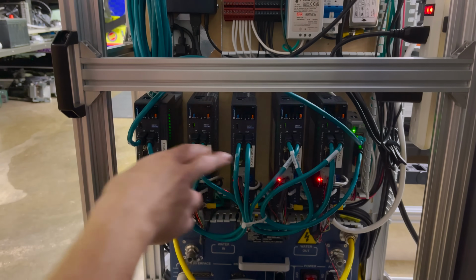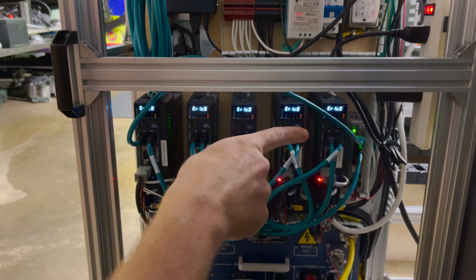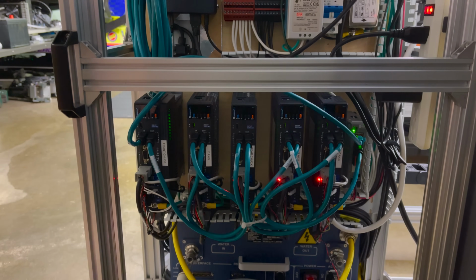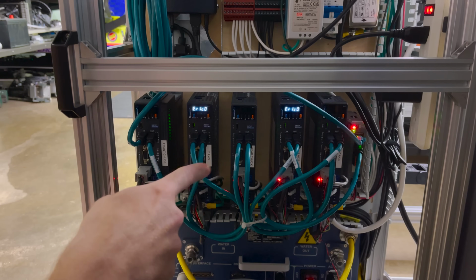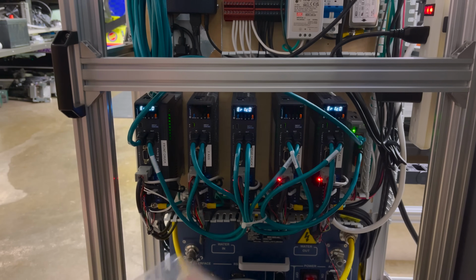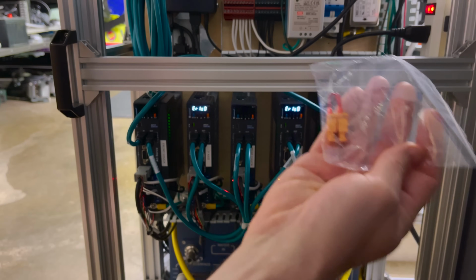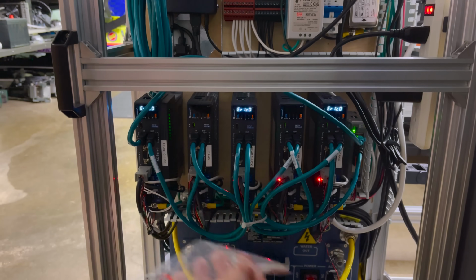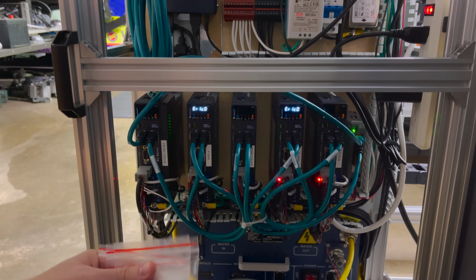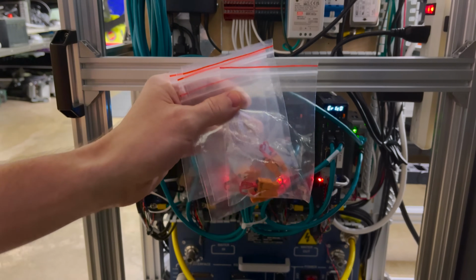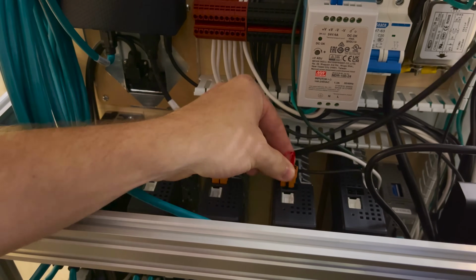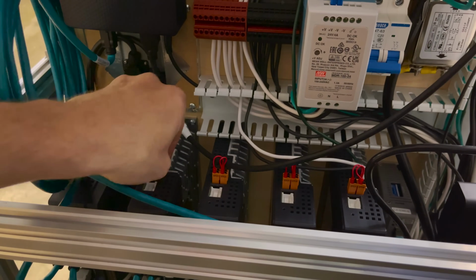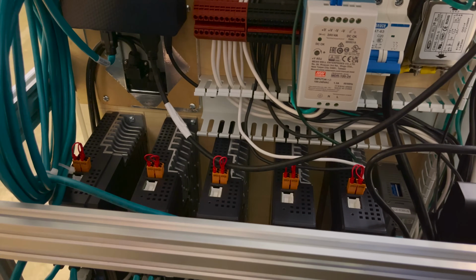When I power on the drives, they're all coming up with this error, and I looked it up, and it's an STO error. The STO function is enabled by default, and I just realized in the boxes it came with these little plugs with some jumper cables to disable it until I can get it wired up to an e-stop. So I guess I need to get all these plugged in. It looks like they plug in right here on the top. Let's see what happens now.